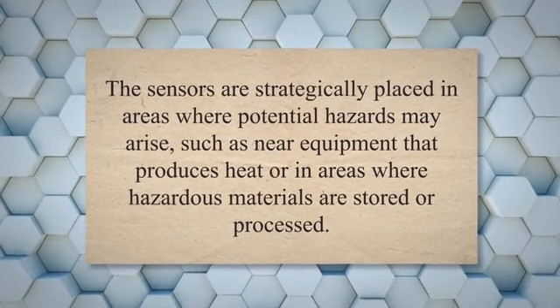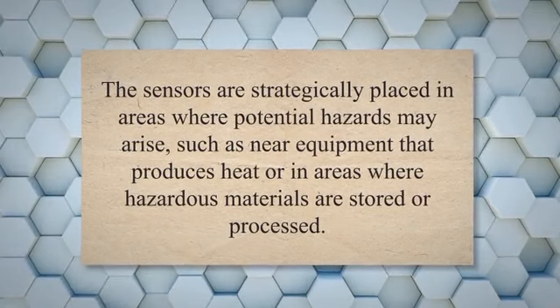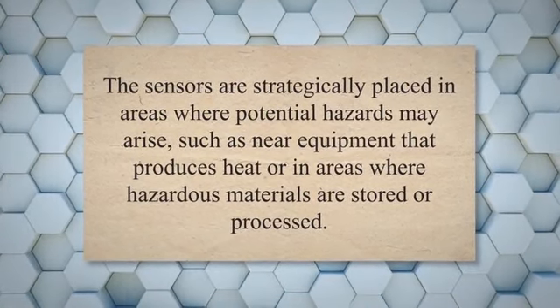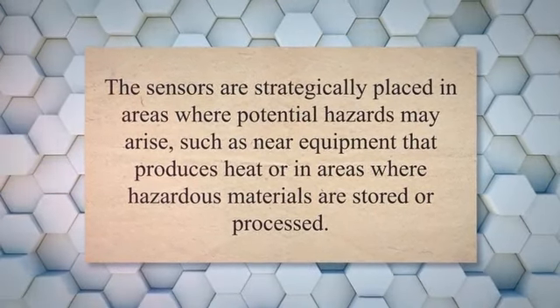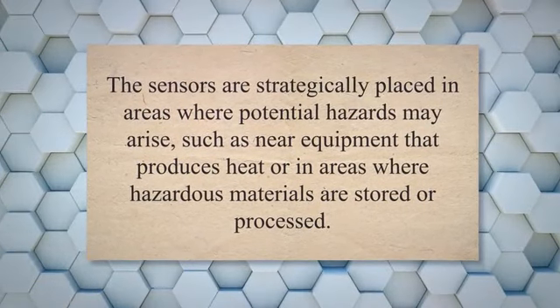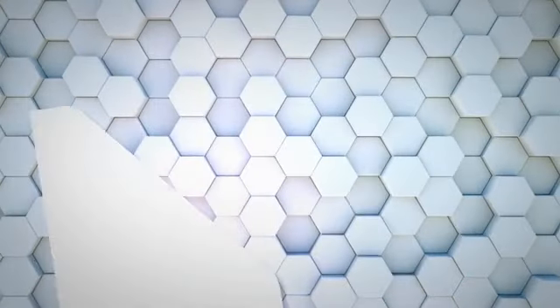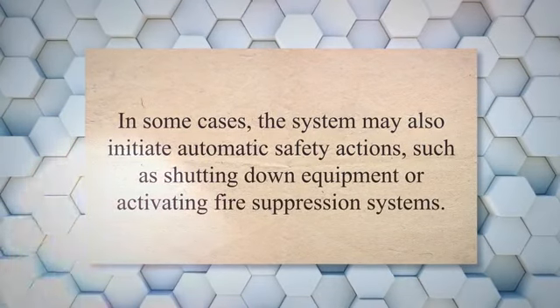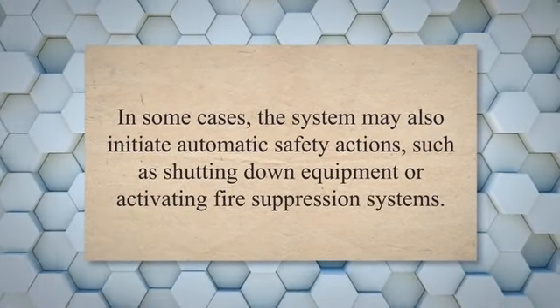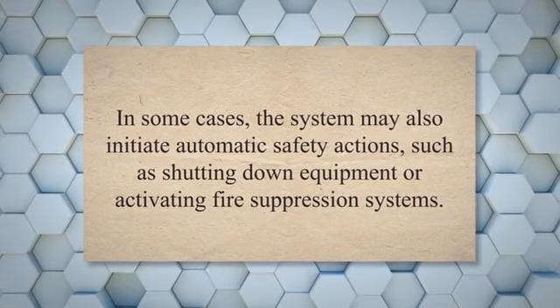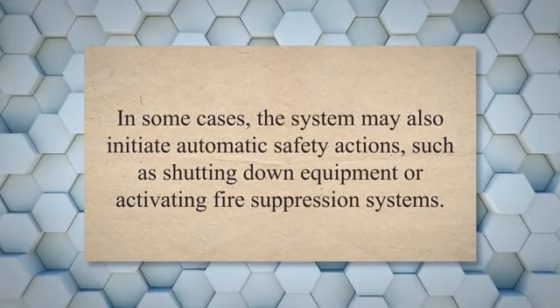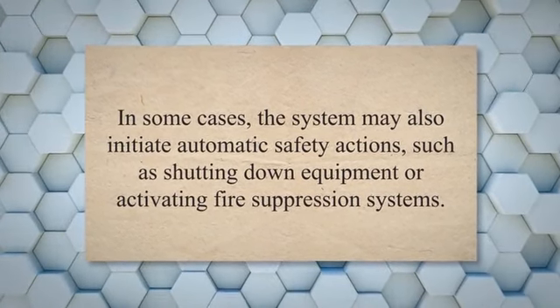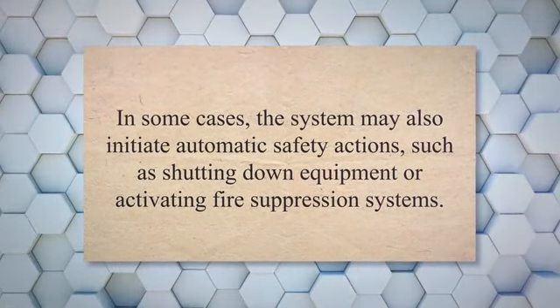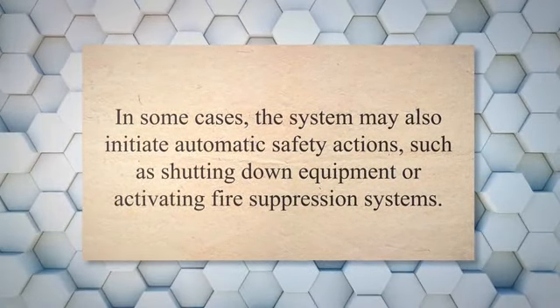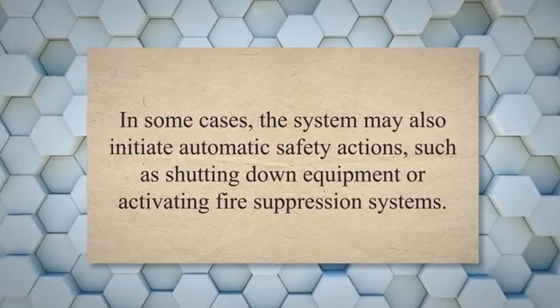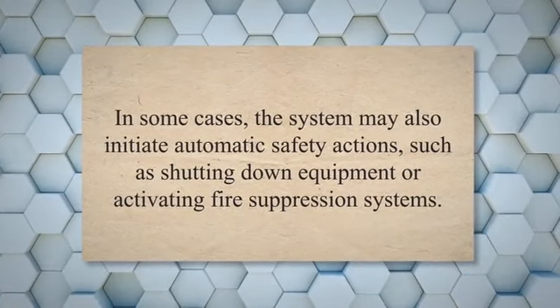The sensors are strategically placed in areas where potential hazards may arise, such as near equipment that produces heat or in areas where hazardous materials are stored or processed. The sensors continuously monitor the environment for the presence of gas or fire, and when a hazardous condition is detected, the control panel alerts personnel through visual and audible alarms.